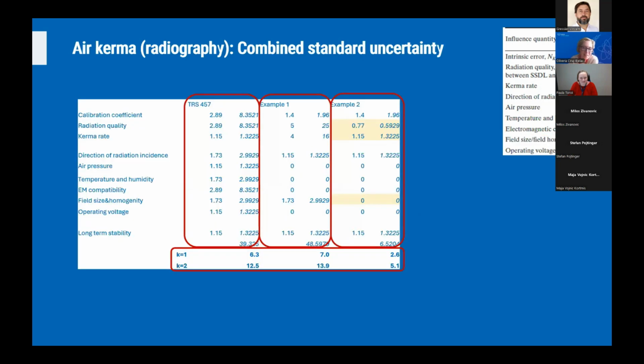So to summarize this walk through the different components of the uncertainty budget, we as medical physicists have in our hands some of the components of the uncertainty budget that can be controlled from local measurements and from our experience in the literature, and that can make our air kerma measurements more accurate than average in clinical conditions. On these slides, you can see one example of an uncertainty budget of the air kerma in radiography from the Agency Code of Practice for Dosimetry in Diagnostic Radiology, and two examples that were used in the previous slides. Depending on how well we control radiation quality and energy dependence of the dosimeters and dependence on the kerma rate, for example, field size and homogeneity, the expanded uncertainty of the air kerma measurements can be reduced from 14% to almost 5%.